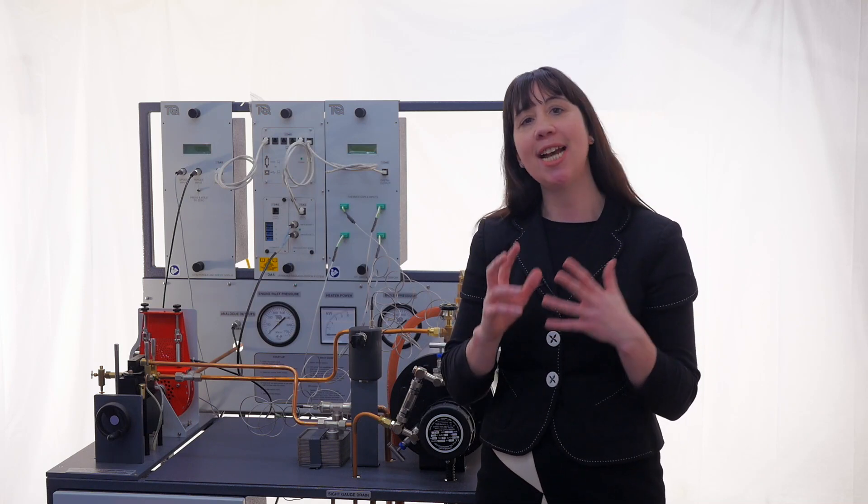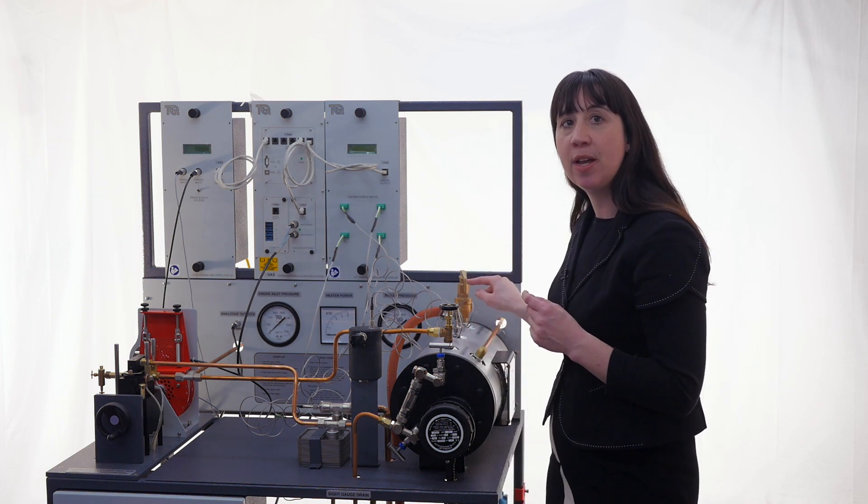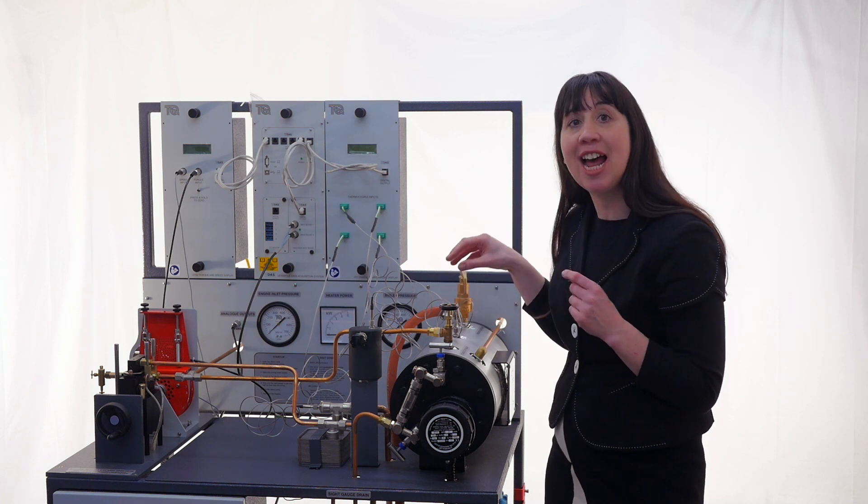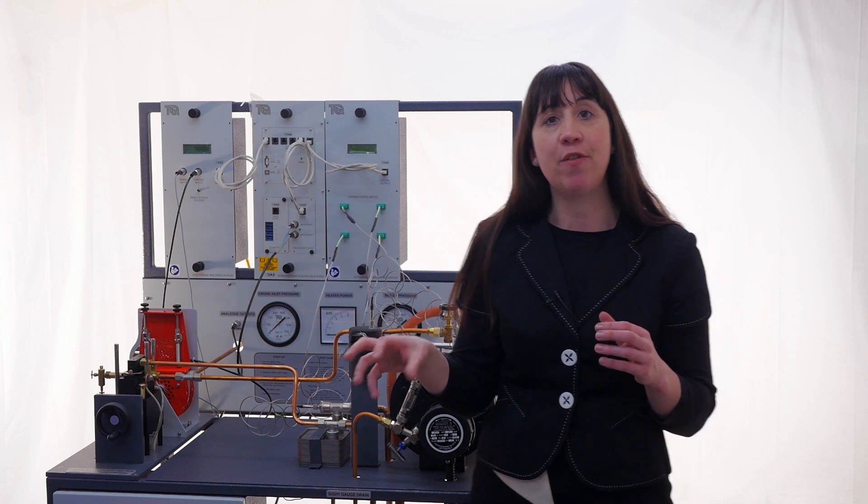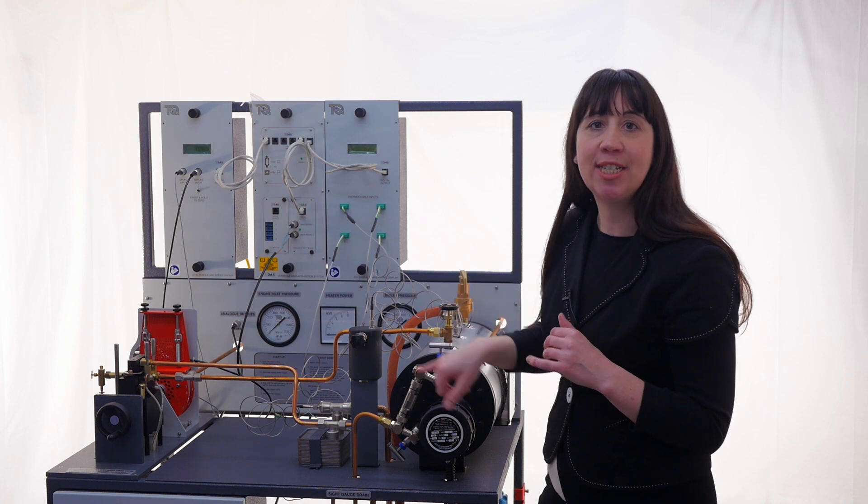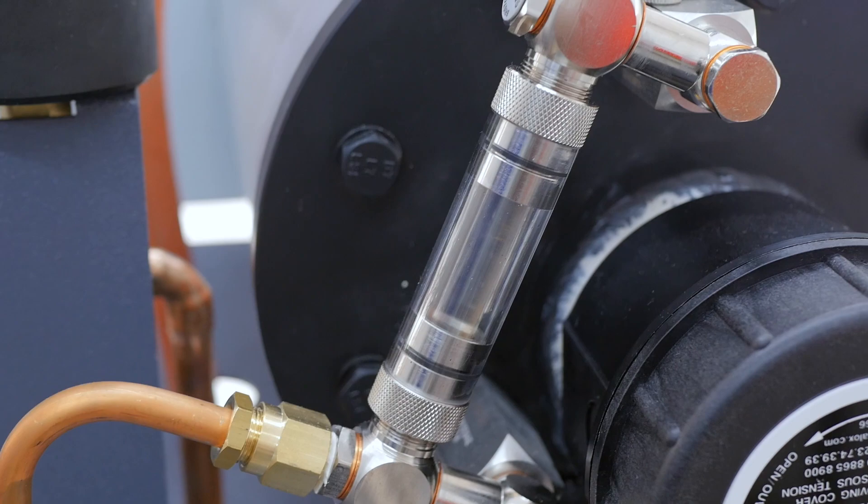To protect against overpressure, there is a spring-loaded pressure release valve here. On the top is a large steam cutoff valve, this bit here, that allows you to regulate the steam flow from the boiler to the engine. At the end of the boiler is a glass sight gauge. This is surrounded by a clear safety shield where you can see the level of water in the boiler.